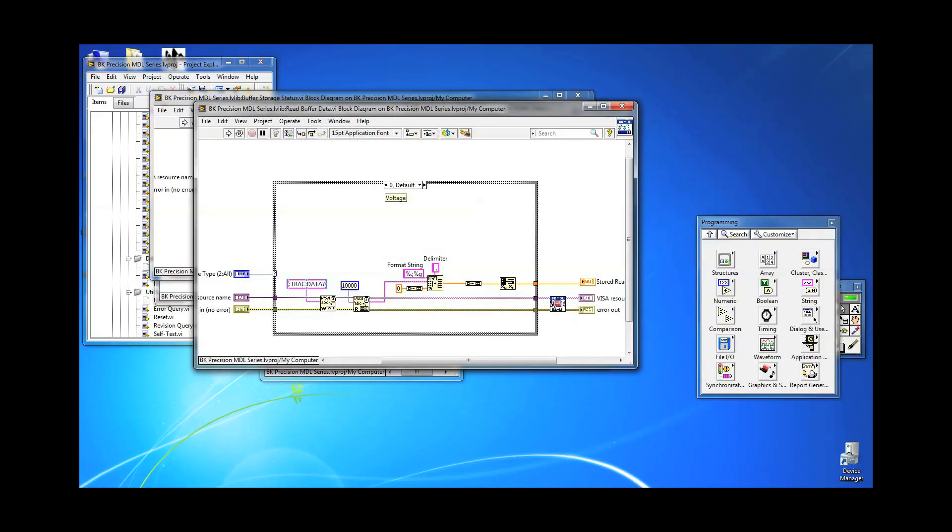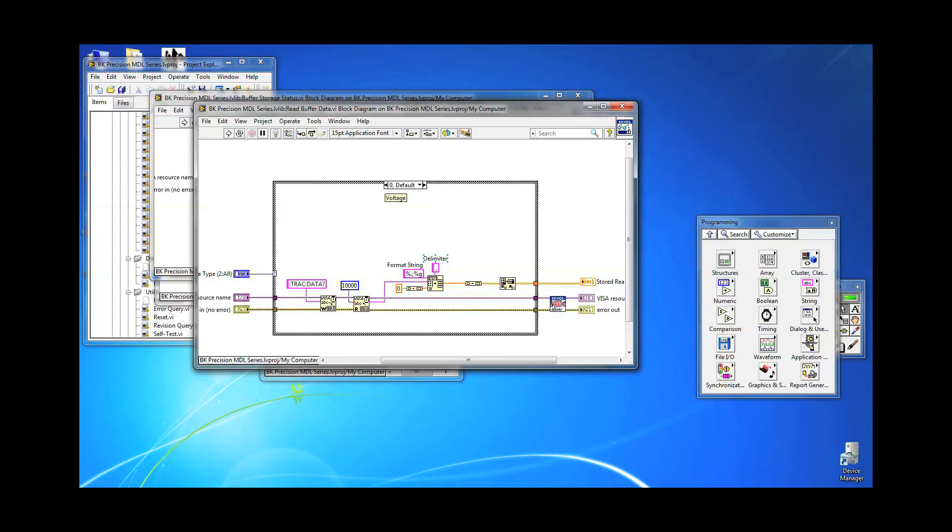Now to query the stored voltage data, send TRAC:DATA?. Make sure you set enough bytes in the read buffer to read all the data. Each reading will be separated by a comma. If voltage and current readings were selected, it will follow the format of voltage, current, voltage, current, and so on.